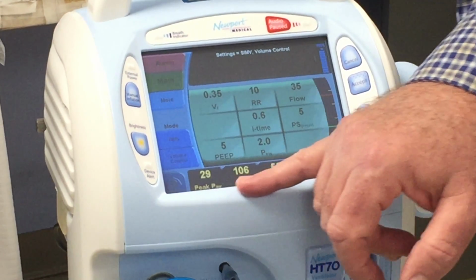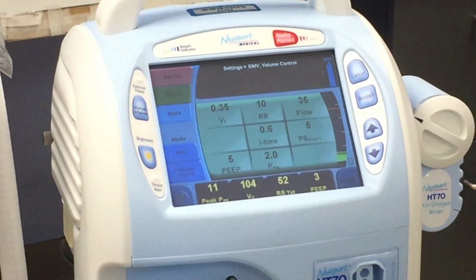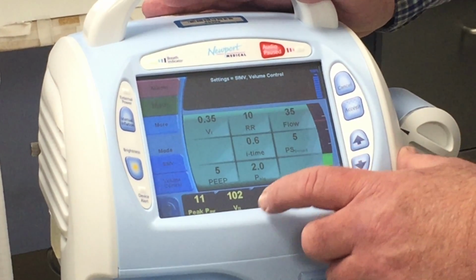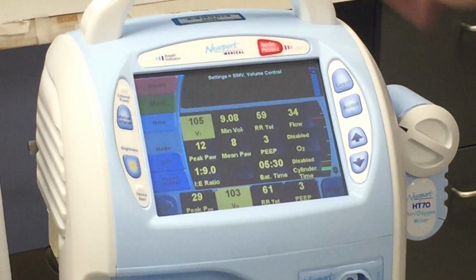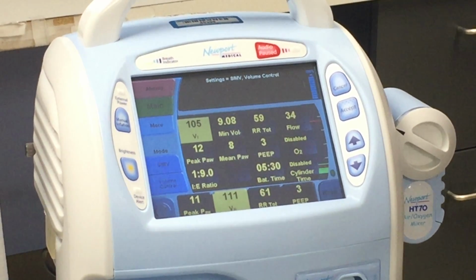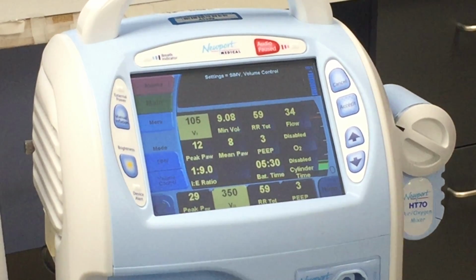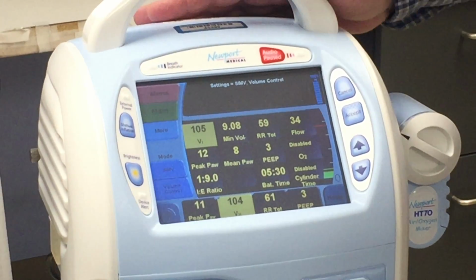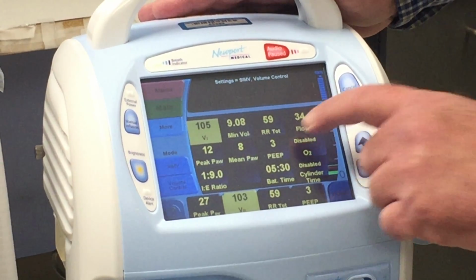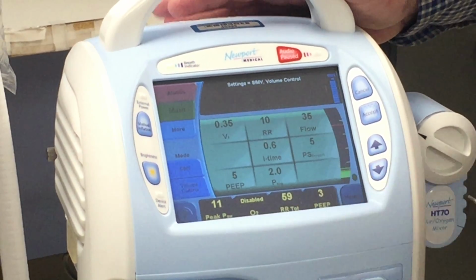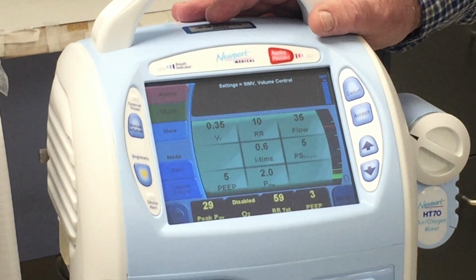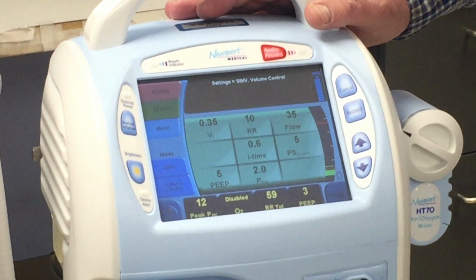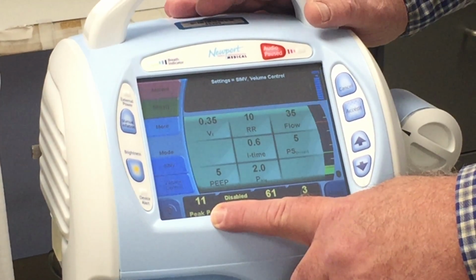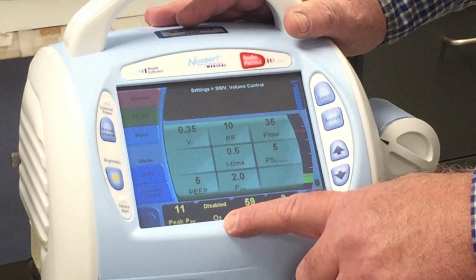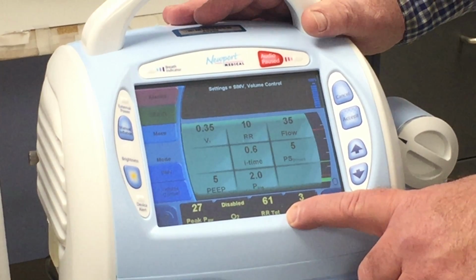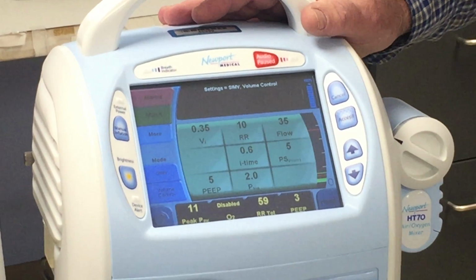Okay. Down here at the bottom, these four parameters are our monitor parameters. If you touch any of them, you can see there's a whole additional screen of parameters that you can move down here. If I want to use O2, right now it's disabled, but it would give us our FiO2 down here at the bottom, which would be our analyzed FiO2. You can see right down here we have our peak pressure. This would be our FiO2. This would be our total respiratory rate, and then our PEEP as well.